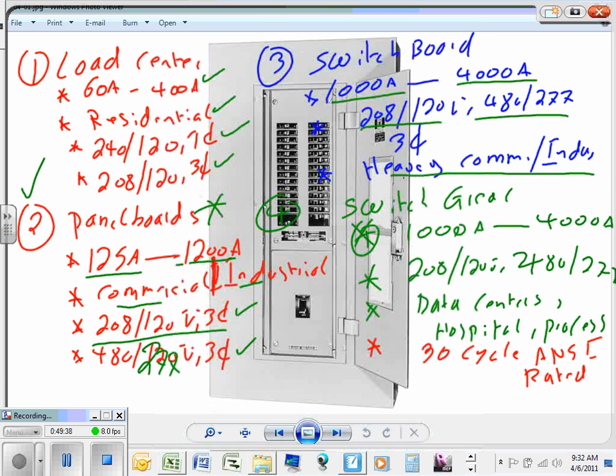Switchgear and switchboard, guys, if you're looking at them, you wouldn't even know the difference. They look alike. It makes a lot of sense to go from 1,000 all the way to 4,000, and they even make 5,000, like he said. The voltages are the same. Where would you use them? In data centers, hospitals, process equipment, anything where the reliability of the system is very important. If downtime is a big issue for you, switchgear comes to your mind.